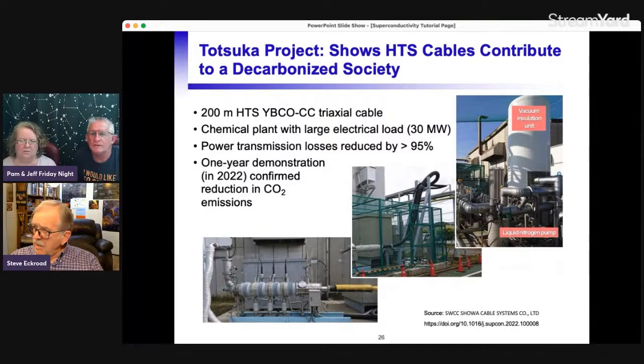The middle picture shows some of the cable going up and bending around the corner of the building, and the upper right shows the cryogenic system. There are different ways of doing cryogenics, but many projects today use a tank of liquid nitrogen, then pump on it to get it a little colder so it works better, and circulate it through the vacuum envelope. This is done because it's easy to get liquid nitrogen in most industrialized countries, delivered by truck. Most economic studies show it's better to just buy the liquid nitrogen and let it boil off than to use a closed loop refrigeration system.